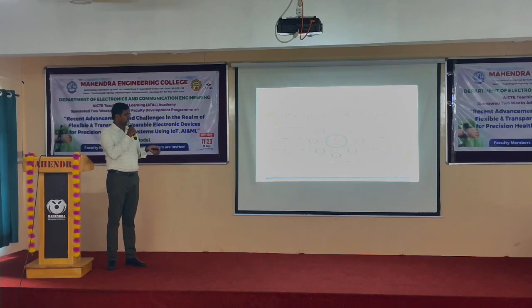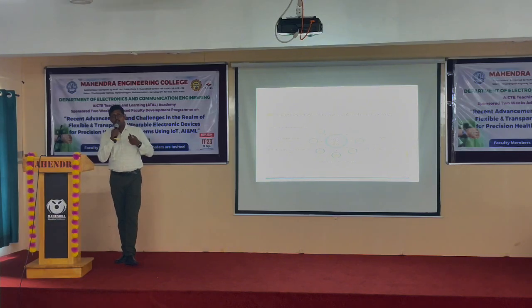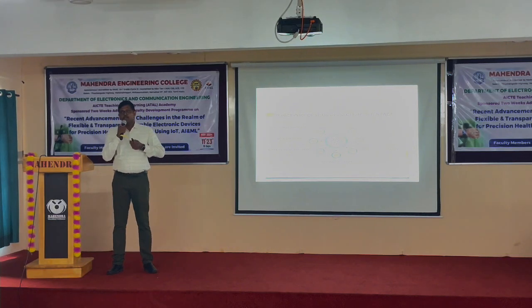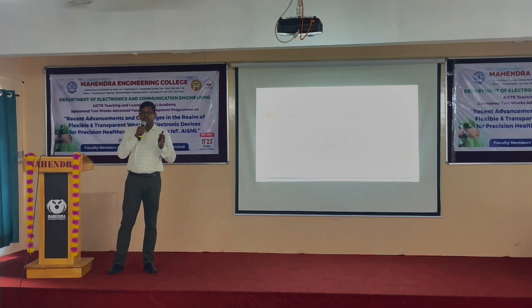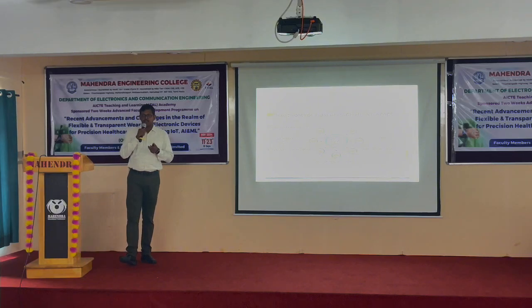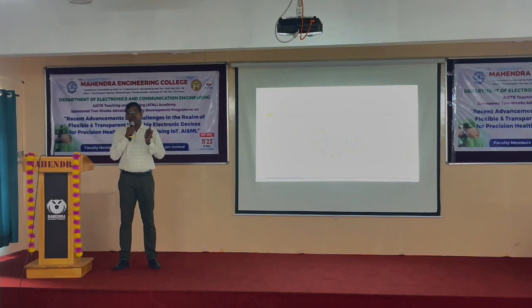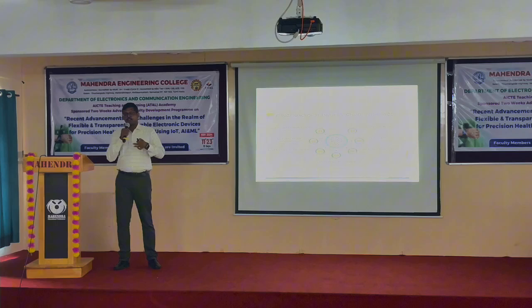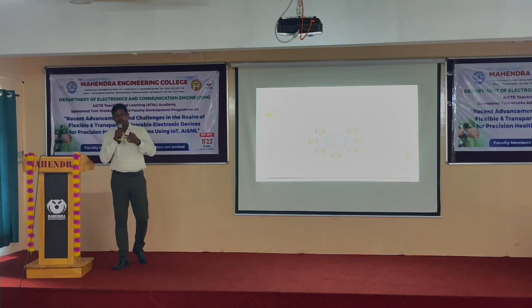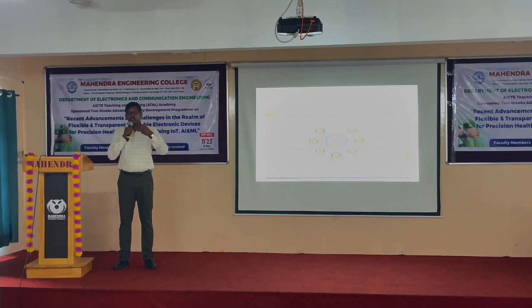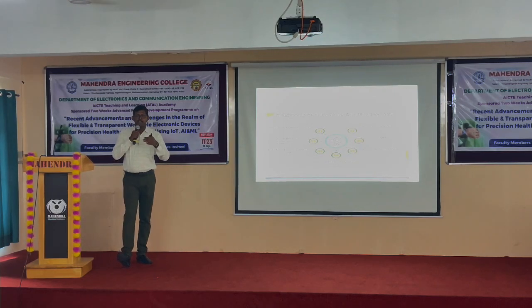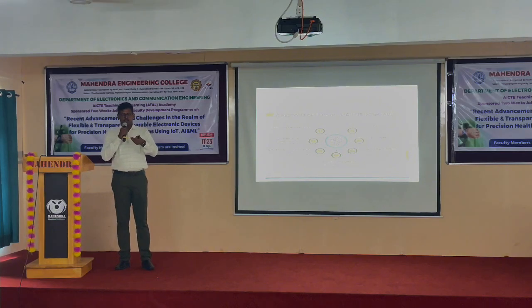So how you are logging the data, like history monitoring. If you see any medical device, it has to keep the history. For example, the multi-para monitor or the critical ventilator connected to the patient has to maintain a history of around 48 hours to 72 hours. It's based on the environment. So why is it required? The doctor can see how the patient improves during the day, something like that. So the history also has to be displayed in a better readable format, so the doctor or the user can easily interpret it and draw some conclusion from that information.